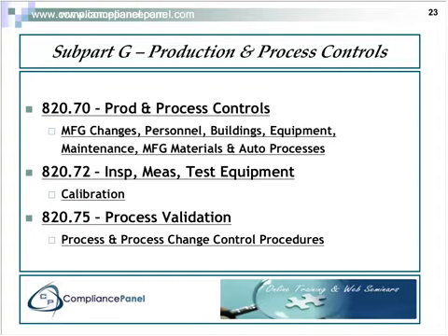But where you design your own test equipment, you may have a test fixture, or you may have a subassembly that's like a golden sample that's going to be used to verify your other parts of the device or even the device itself, you have to include those as part of your calibration or your preventive maintenance process, and these items are validated periodically so that you know that anything in-house is still working in the same manner as it was designed to be used.